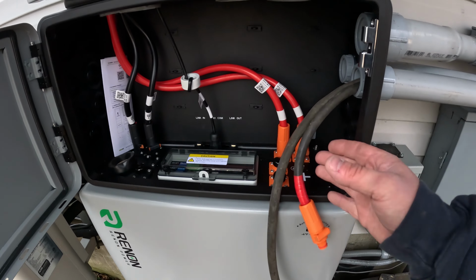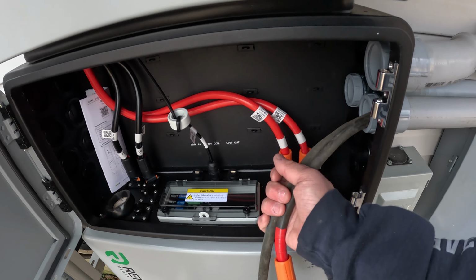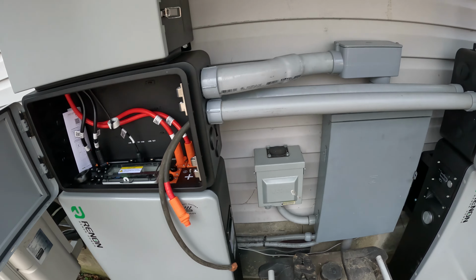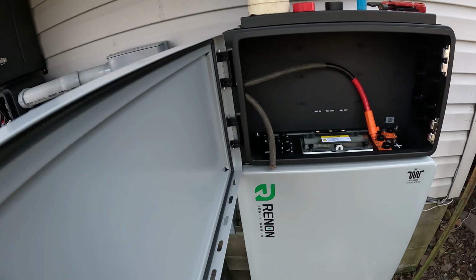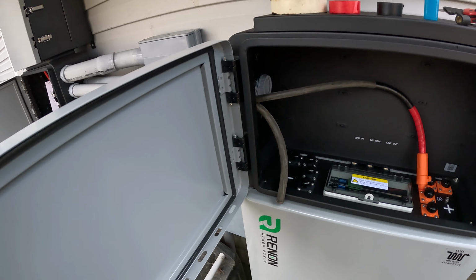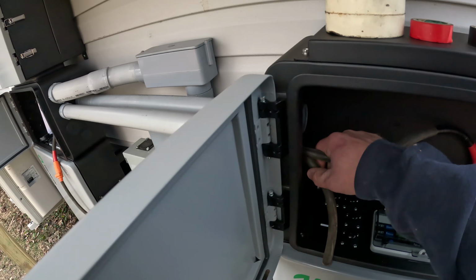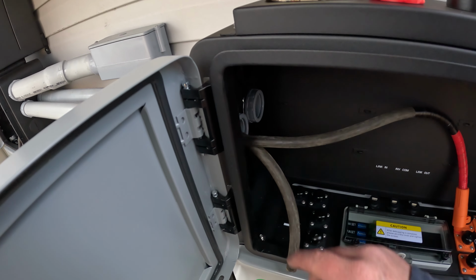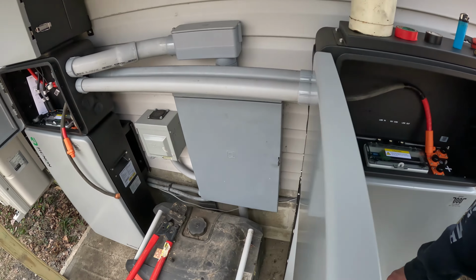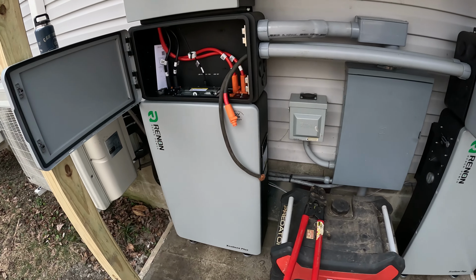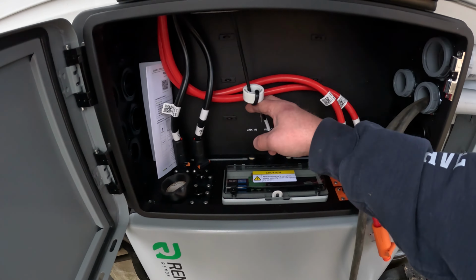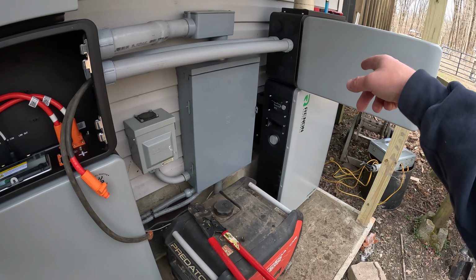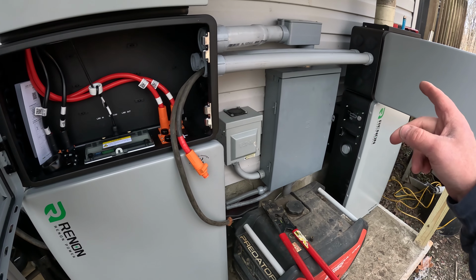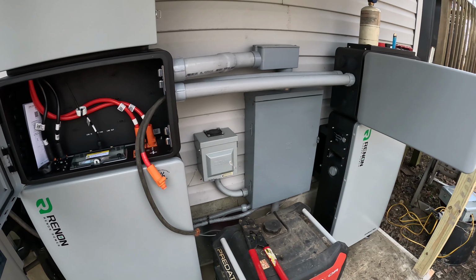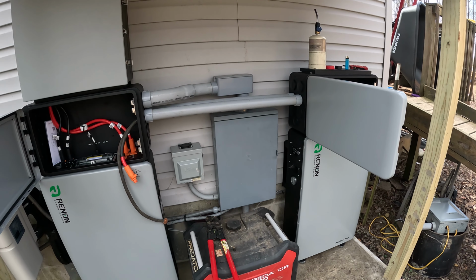Well, we're back out here this morning and we're working on our 2-aught connecting leads that run between the batteries. We're going to have 2 sets of these, one positive, one negative, in each conduit, and that should get us all tied together. Then I'll be running a communication wire between this battery and that battery as well as a ground. But yeah, we're getting there slowly but surely.